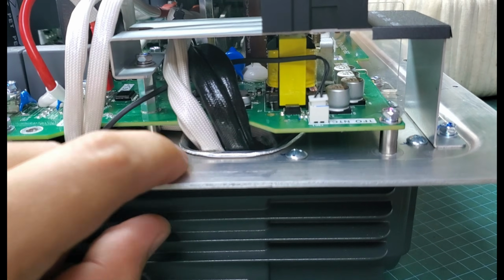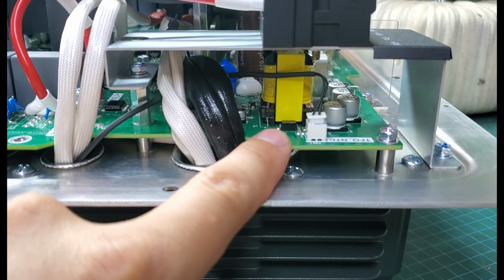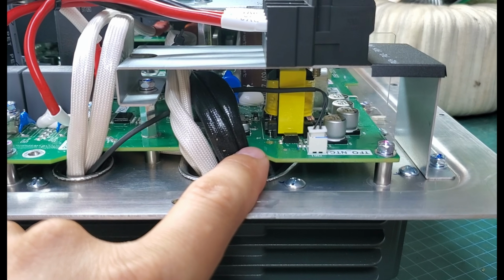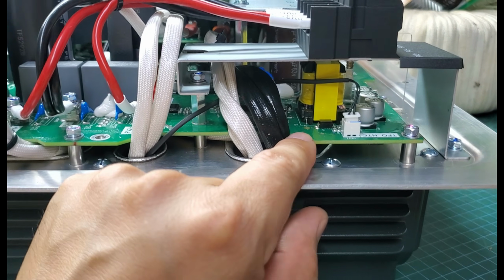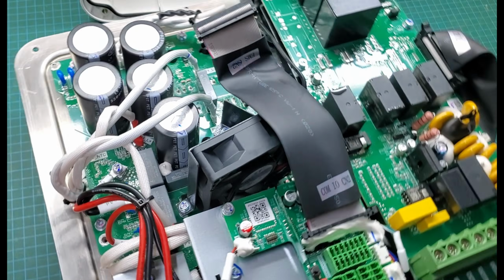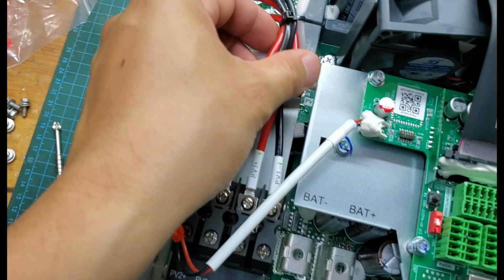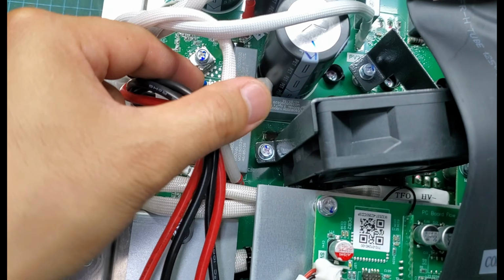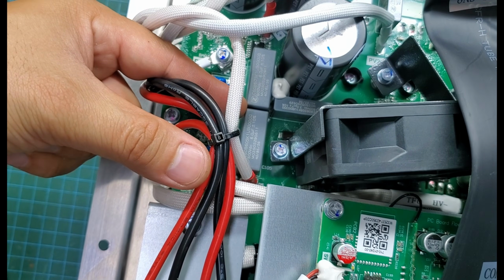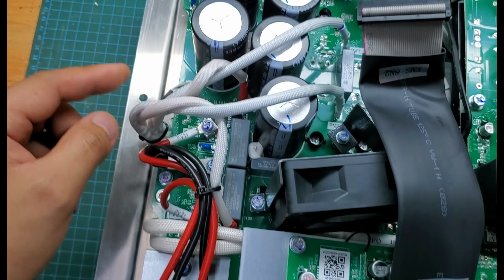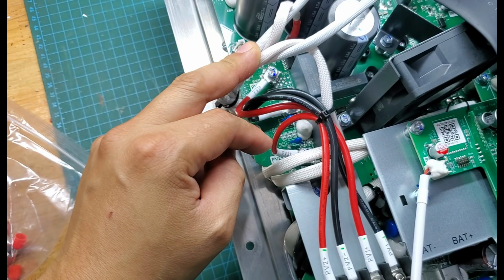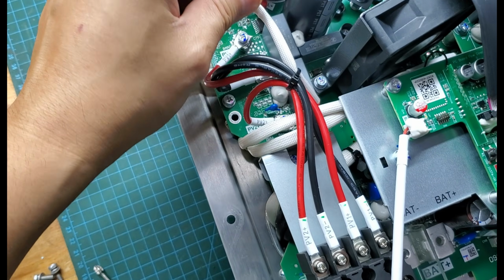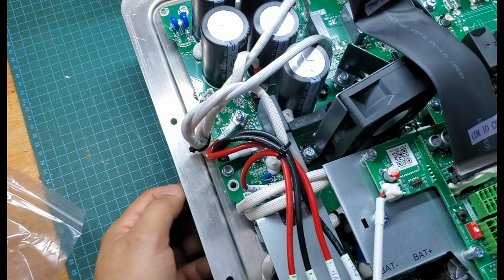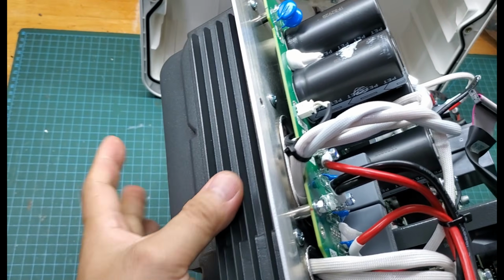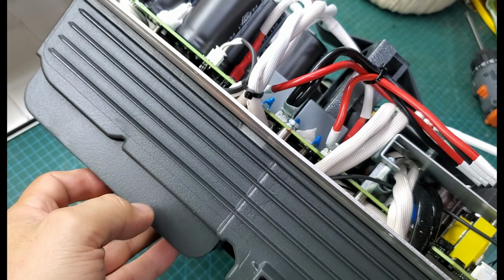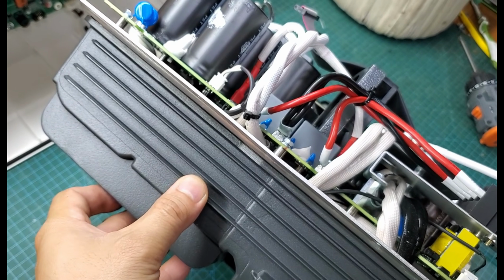This small yellow transformer is part of the auxiliary power supply. It steps down the battery voltage into stable rails like 12 volts, 5 volts, and other required levels to power the inverter's internal control modules. This inverter features 2 independent MPPT inputs, which means you can connect 2 separate solar arrays with different panel counts or orientations without worrying about reduced energy harvesting efficiency. It uses a boost-type MPPT topology, where the voltage from the solar panels is stepped up to around 400 volts. This is achieved through IGBTs and boost inductors, which are tightly potted and mounted onto a large aluminum heatsink at the back for effective thermal management.